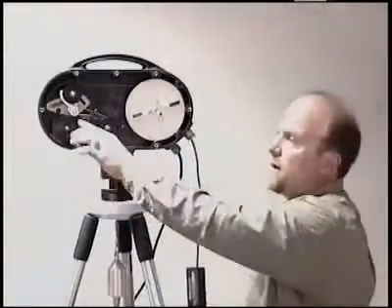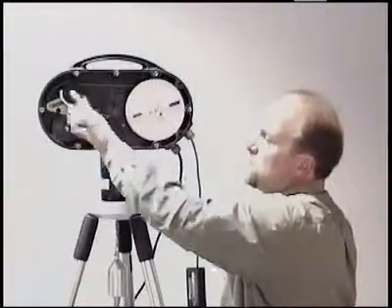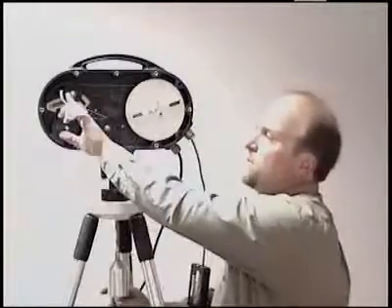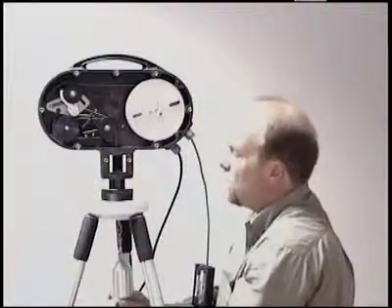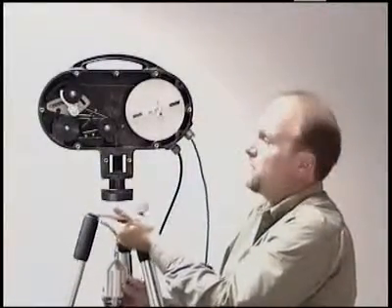The idler arm function is when it goes down and takes a measurement. When it touches the surface of the material the idler arm comes back slightly to take up the slack, and then the motor pulls the weighted probe back to the neutral position at the top of the vessel.